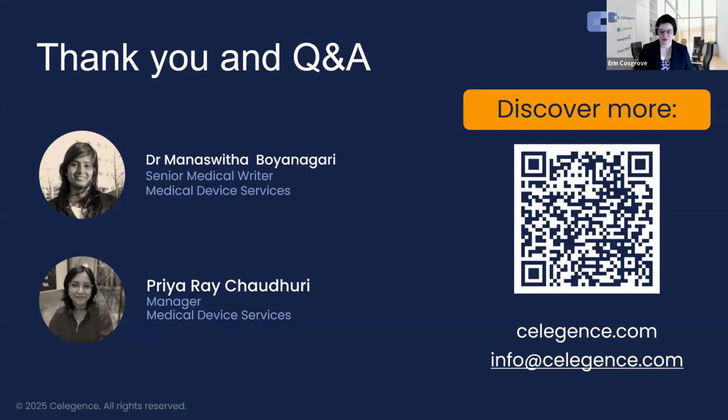What level of clinical evidence are notified bodies looking for in new devices in well-established technologies? The example this person gave is such as dental filling materials. Yeah, so dental filling material calls for class 2A or class 2B, depending on the intended purpose. If it is a well-established technology, definitely it is expected that the manufacturer has most of the data already generated based on the state of the art.